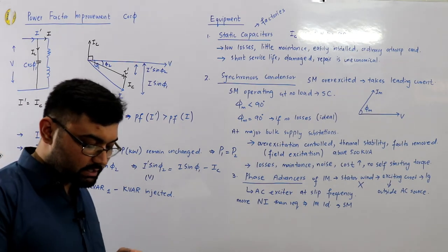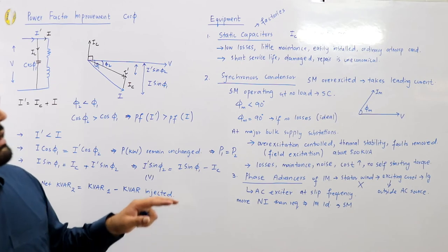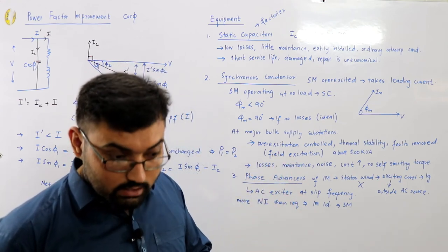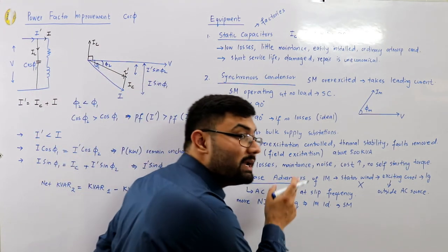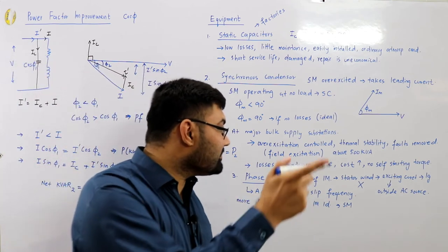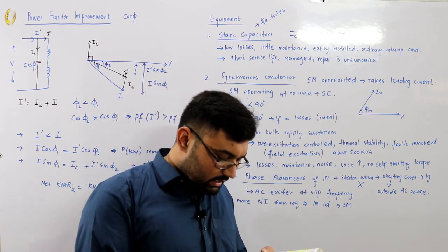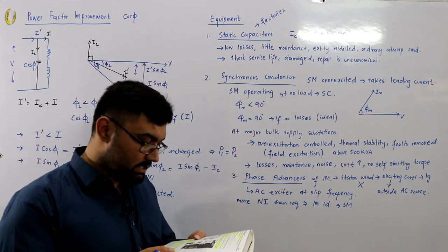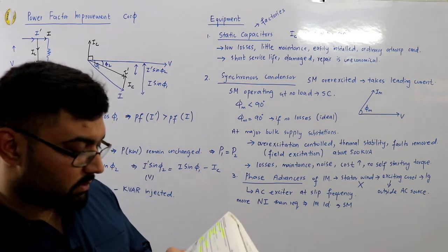Phase advancers have two principal advantages. Firstly, as the exciting ampere turns are supplied at slip frequency, the lagging kVARs drawn by the motor are reduced. The AC exciter will also draw lagging kVARs, but the lagging kVARs of the motor have been reduced. Secondly, phase advancers can be conveniently used where the use of a synchronous motor is inadmissible. However, the major disadvantage of the phase advancer is that they are not economical for motors below 200 horsepower.